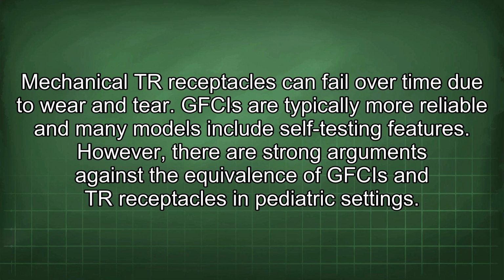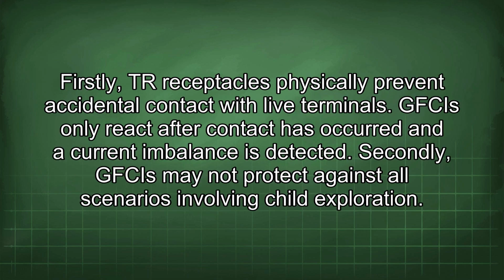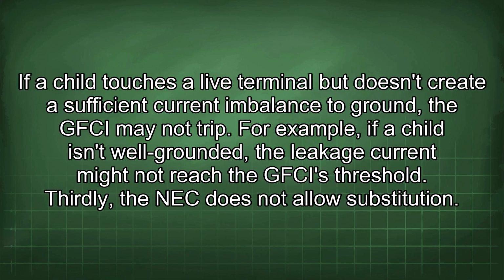However, there are strong arguments against the equivalence of GFCIs and TR receptacles in pediatric settings. Firstly, TR receptacles physically prevent accidental contact with live terminals. GFCIs only react after contact has occurred and a current imbalance is detected. Secondly, GFCIs may not protect against all scenarios involving child exploration. If a child touches a live terminal but doesn't create a sufficient current imbalance to ground, the GFCI may not trip. For example, if a child isn't well grounded, the leakage current might not reach the GFCI's threshold.